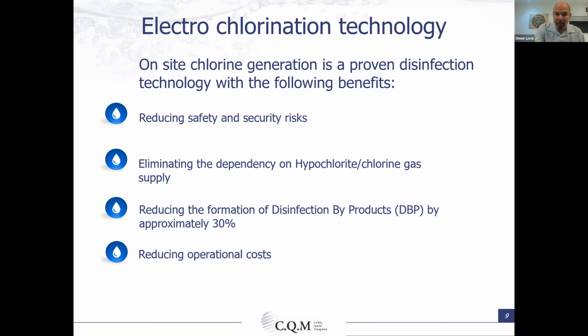And there is a big advantage of reduction of the DBPs by using this type of chlorination. It's proven not only for our technology, but also other electrochlorination technologies out there, that this type of chlorination produces about 30% less DBPs than just hypochlorite or chlorine gas, and this is really a factor. These DBPs are not healthy for any of us. And there's also a reduction of operational costs.